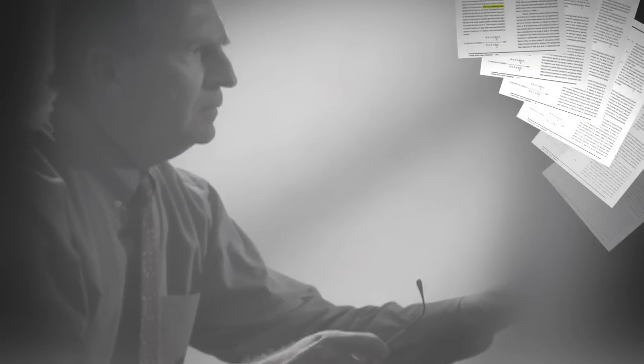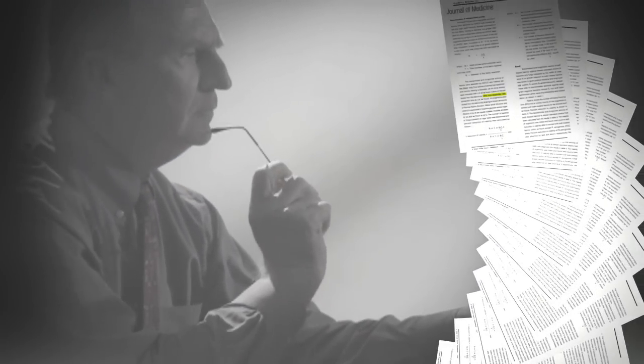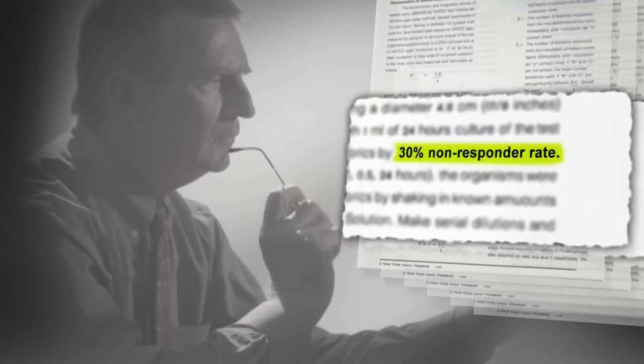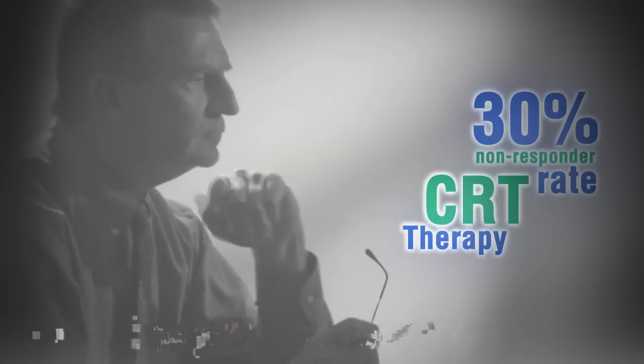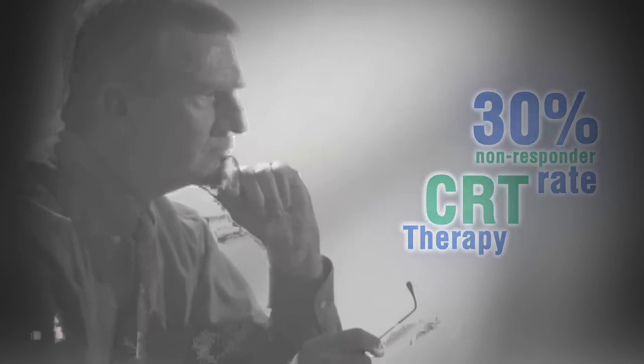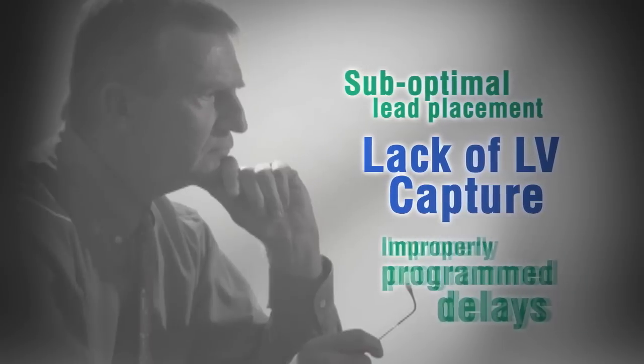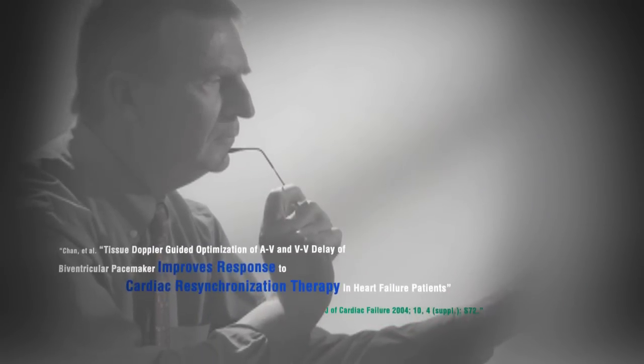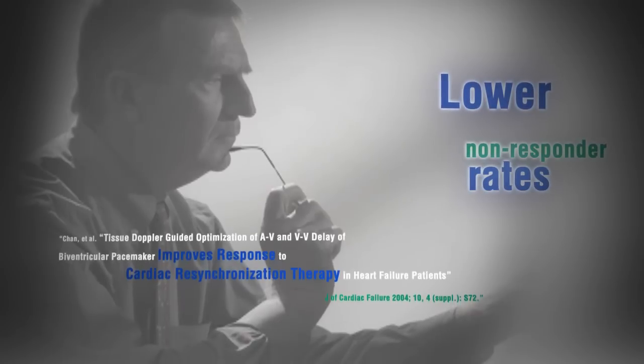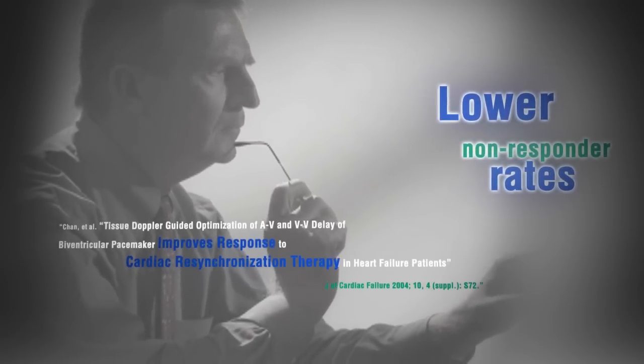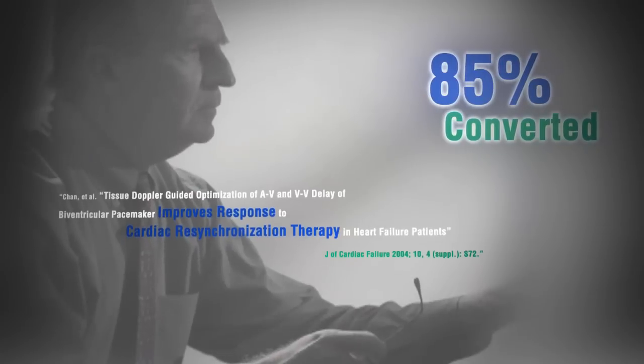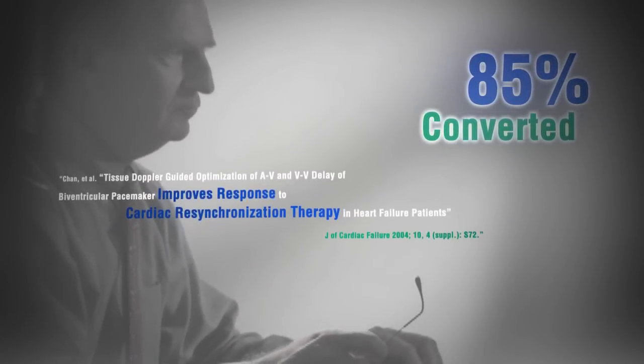The management of non-responders to CRT therapy continues to be a challenge to clinical practices today. According to literature, up to 30% of CRT patients fail to respond to CRT therapy. While many factors such as suboptimal lead placement, lack of LV capture, and improperly programmed delays play a part in the non-response to CRT therapy, there are options available to the clinician to improve response and lower non-responder rates. 85% of non-responders in one study were converted by timing cycle optimization.